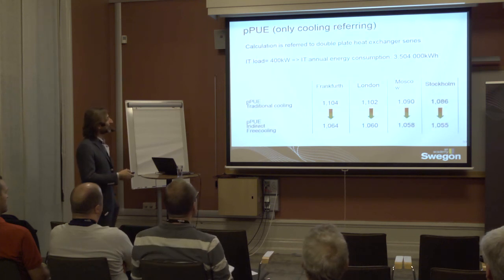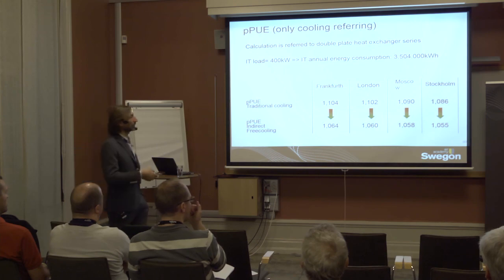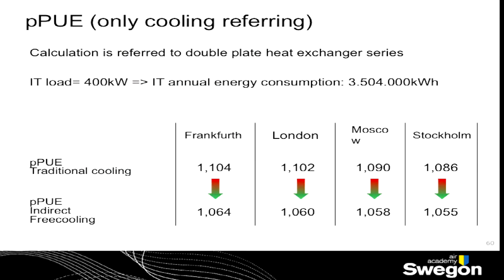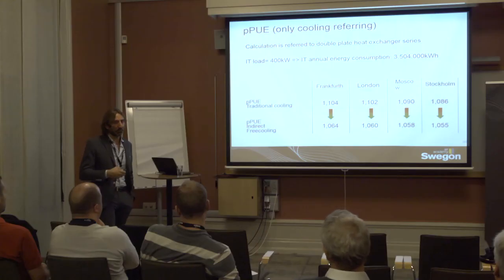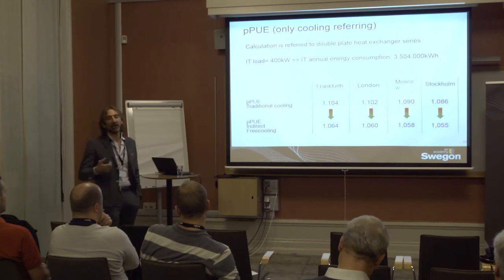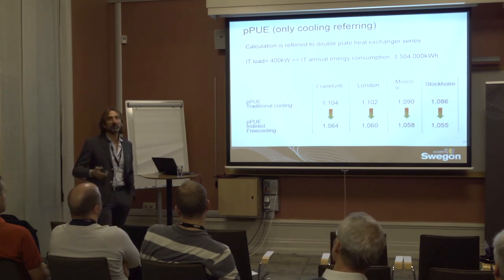And the result that we obtained in terms of partial PUE, of course, not of total PUE, because we cannot take care about the other systems. We cannot take care about battery. We cannot take care about the lighting or something like this. So don't trust who gives you a number for a cooling system and speaks in terms of total PUE, because it's not possible to consider the total PUE. We should speak about EER of the system, but we can speak about the partial PUE just in the same way, because if you have got a free cooling system with an EER of 10, it means that you have got a partial PUE of 1.1, nothing more than this.